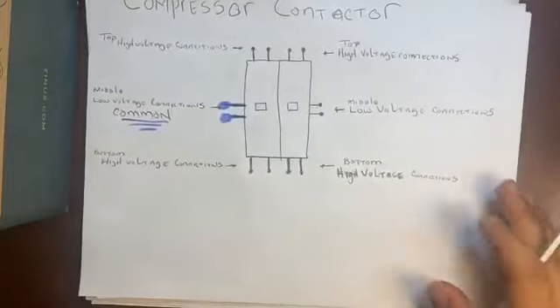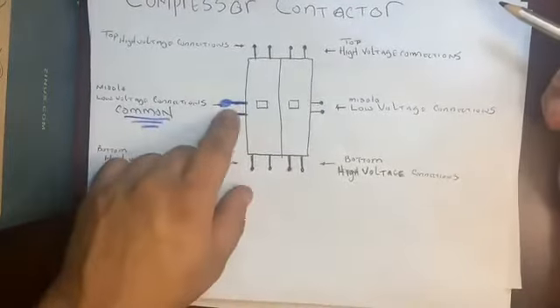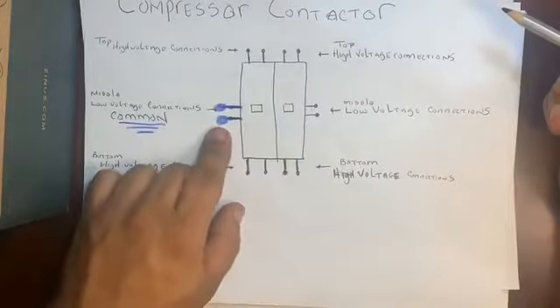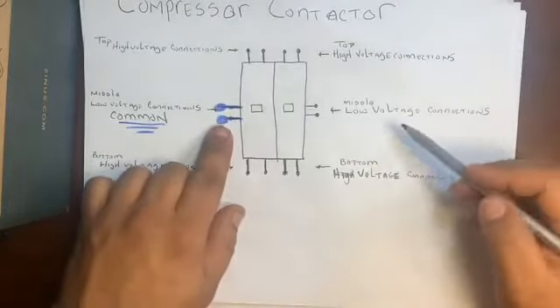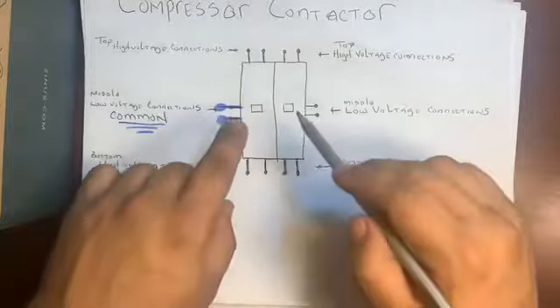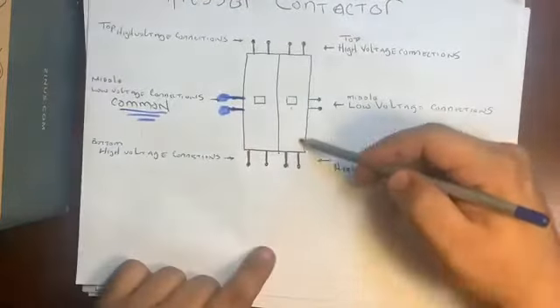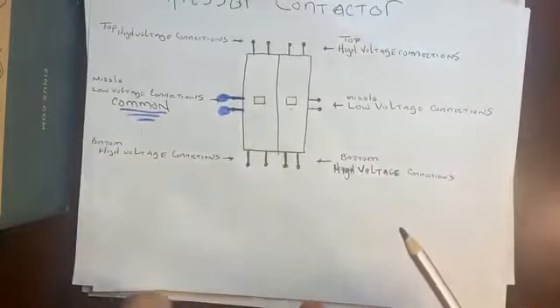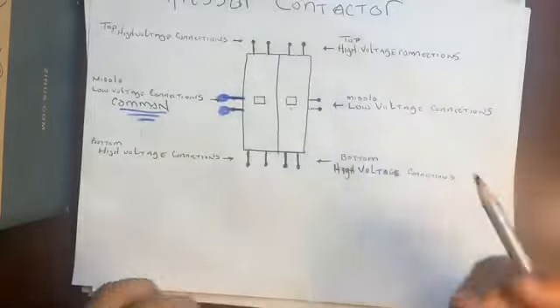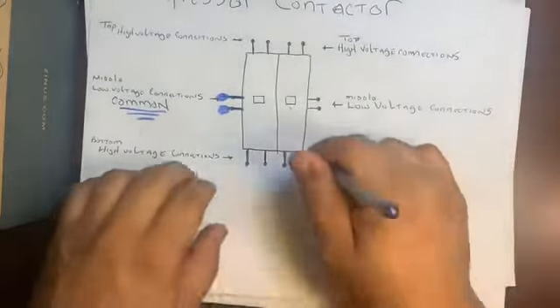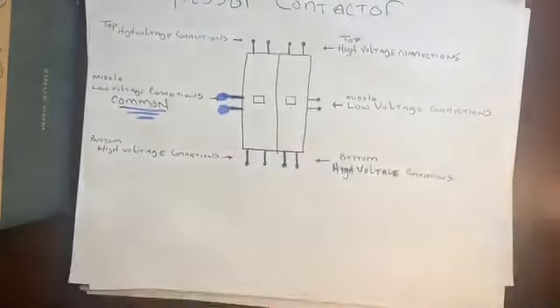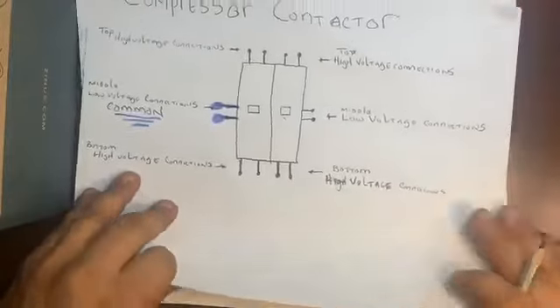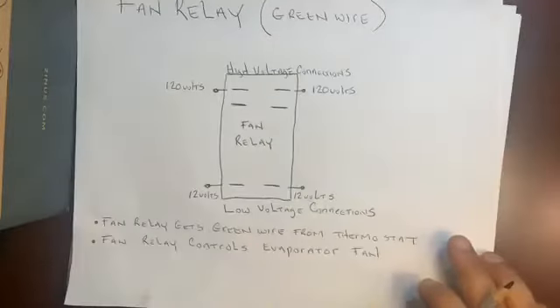Common leg, common, common. Again, a relay is a relay. Every relay has a low voltage common. We got the low voltage common and 12 volts on the low voltage control. Both meet here. The plunger drops and power is streamed through the contactor. And this is the contactor. This is what turns on the compressor and the outdoor fan motor. This compressor contactor is in the condensing unit, not in the air handler. Moving on. Let's go to our fan relay.